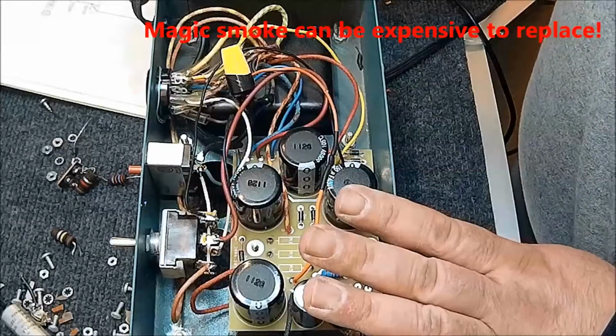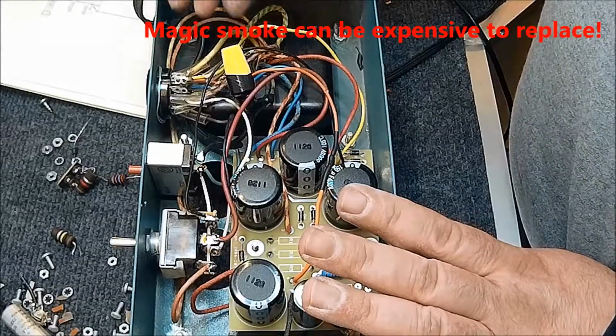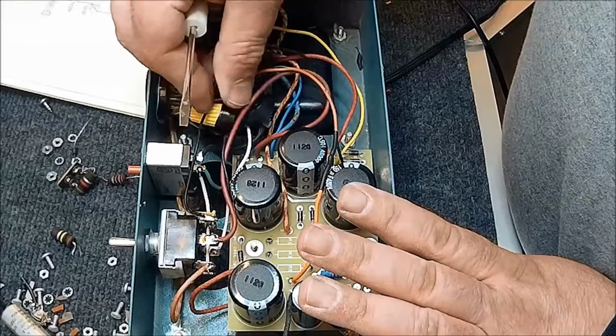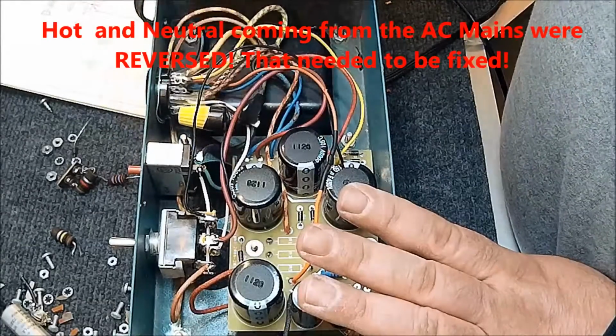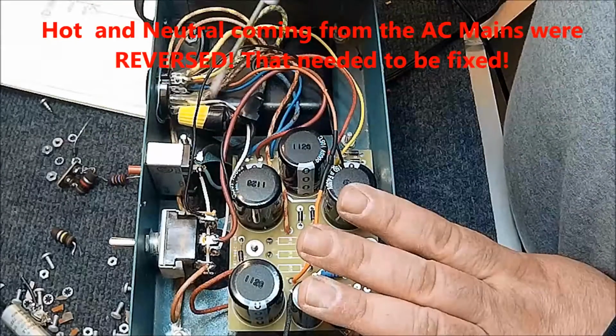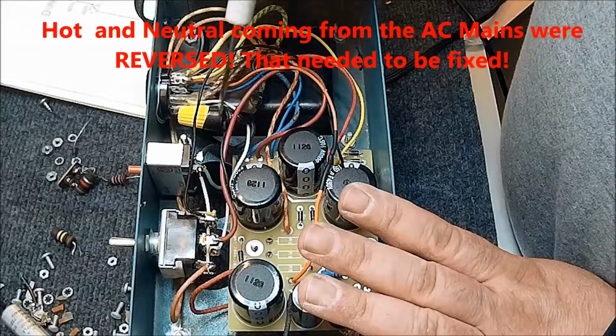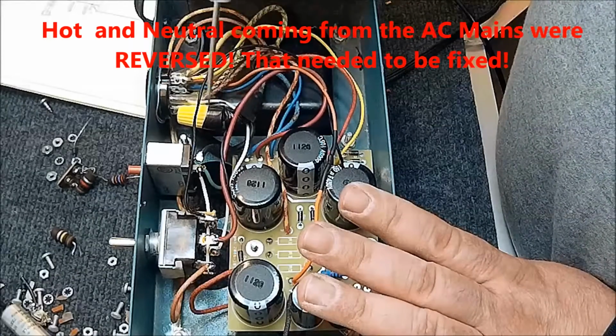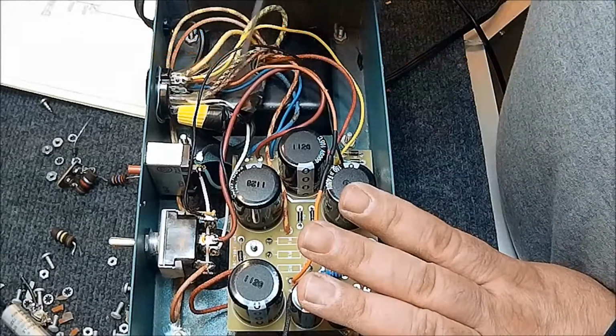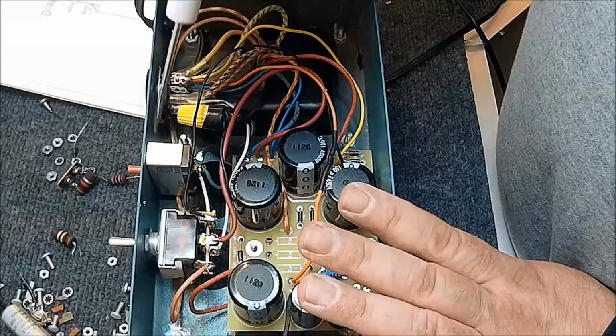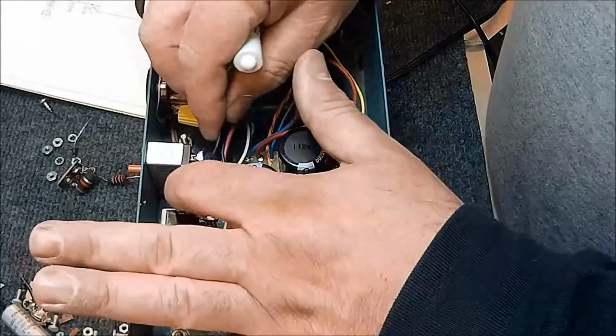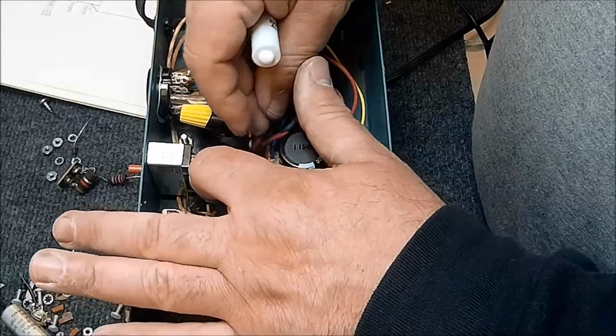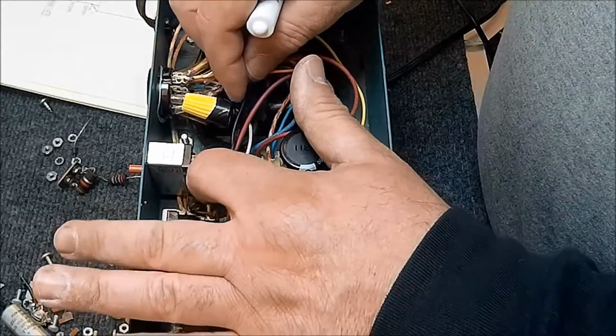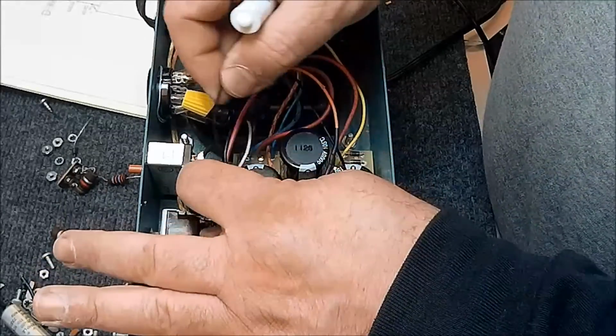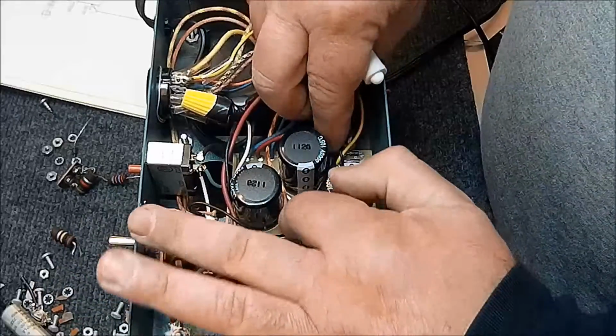My next step is to test. I have to plug this thing in and make sure the magic smoke doesn't leak out. We made one slight modification: we made sure the hot line was not tied directly to the transformer, and the neutral line went through the transformer instead. The hot went through our fuse and switch. You want to make sure those things are routed correctly, especially on an old piece of equipment like this that other people have had their fingers in.